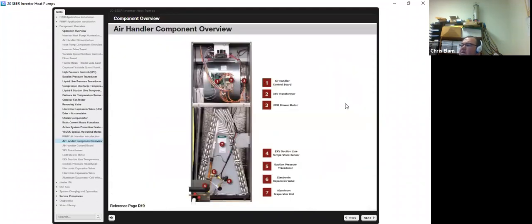Okay, some of the various components we have on the air handler, which is typical. Some are normal, some are a little different than you should see them. You have your air handler control board, your 24-volt transformer. You have an ECM blower motor. These may be new to some of you. Number 4, you have what they call a suction line temperature sensor.